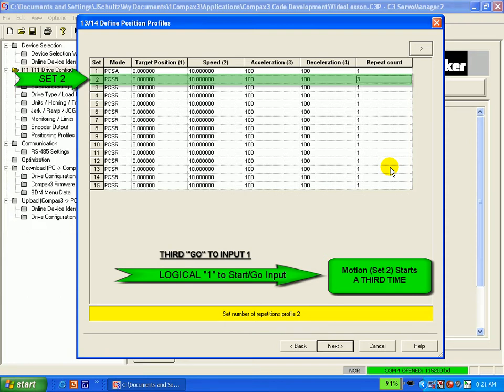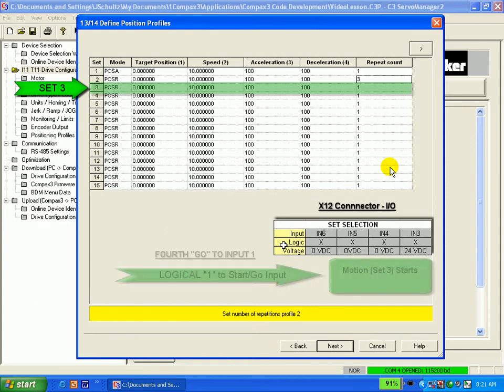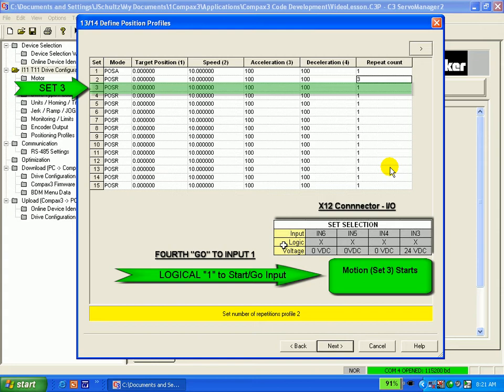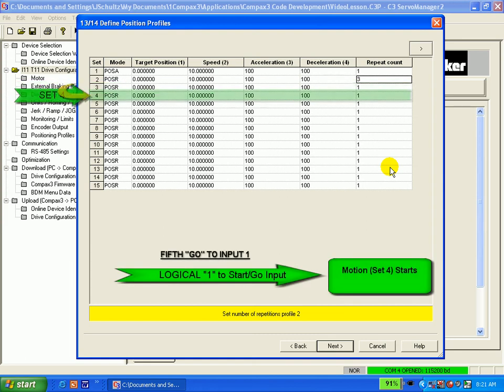Now, the internal pointer is automatically indexed to set number 3 no matter what logical pattern inputs 3, 4, 5, and 6 are at. The PLC sends a fourth GO input and we do set 3 once. The PLC sends a fifth GO input and we do set 4 once and so on.